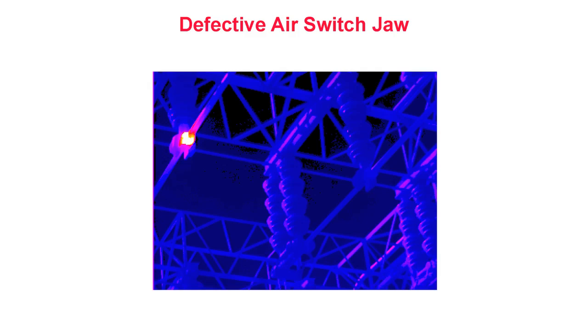Although under the same load, neither of the adjacent switch poles, which are represented in blue, exhibits this type of localized heating. Left unattended, this hotspot will continue to deteriorate until the switch fails, causing an unscheduled outage and downtime. By detecting this problem before it causes an outage, repairs can be carried out during a planned outage. Early detection also allows for the equipment to be repaired rather than replaced, since equipment damage is minimized when catastrophic failure is avoided.